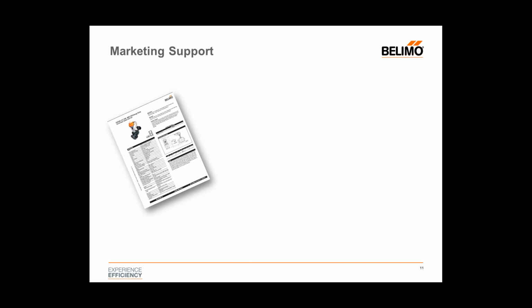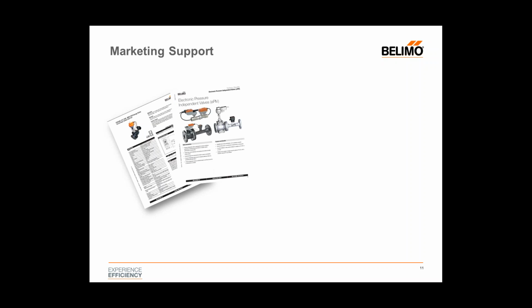Talk about some of the marketing support that's available for both the ePIV and the energy valve. Of course, we have the submittals that are all online on our Belimo website. These can be found for both the ANSI 125 and ANSI 250 ePIV and both energy valve. Those are available via download currently, today as we speak. The technical documentation for the ePIV has been fully updated as well, and it includes the ANSI 250 specification. So now it covers the entire line, all the way from 1/2 inch to 6 inch, covering both ANSI 125 and ANSI 250. So if you're looking for one comprehensive document of all the technical documentation based on the product line, this would be it as well.